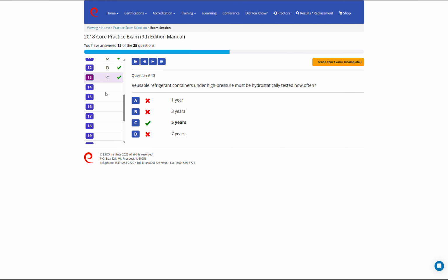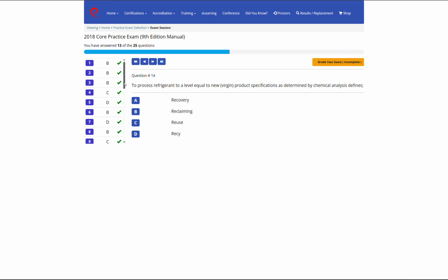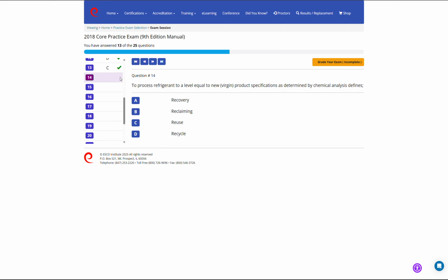That sounds very interesting, but I'm trying to stay focused. But can you glance over what hydrostatic testing even is? Sure. Hydrostatic testing means filling the container with water, cranking up pressure way past normal, like 1.3 times its service pressure. Then checking for leaks or bulges. It's like stress testing it underwater to make sure it'll hold refrigerant safely.